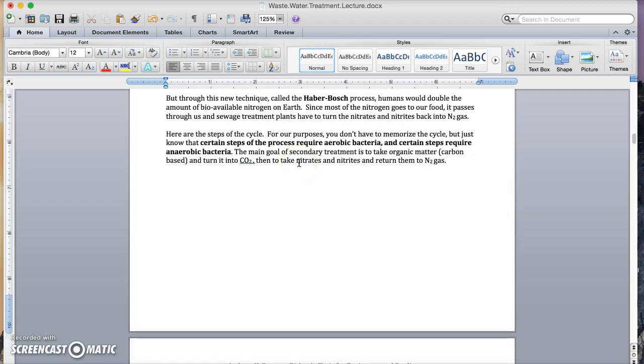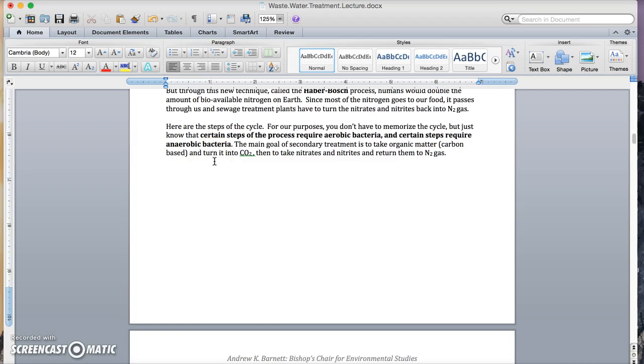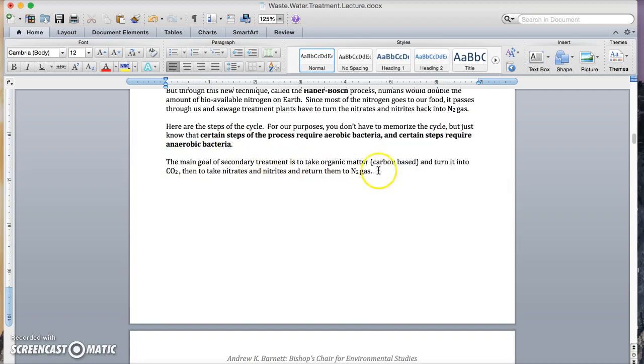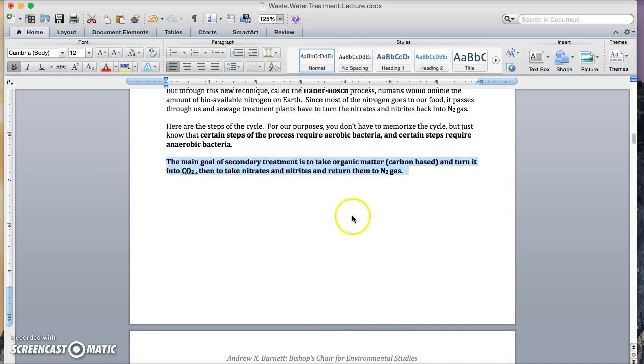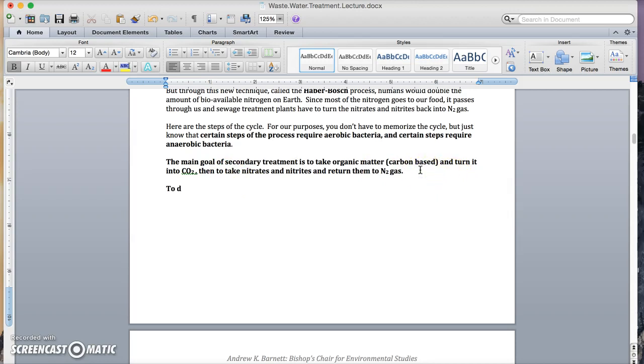So below, you're going to look at the steps of the cycle. For our purposes, you don't have to memorize the cycle, but just know that certain steps of the process require aerobic in the presence of oxygen bacteria. And other steps require anaerobic bacteria. The main goal, and this is really important, the main goal of secondary treatment is to take organic matter, which is carbon-based, and turn it into CO2, then to take nitrates and nitrites and turn them into N2 gas. To do this, we need both aerobic and anaerobic conditions.